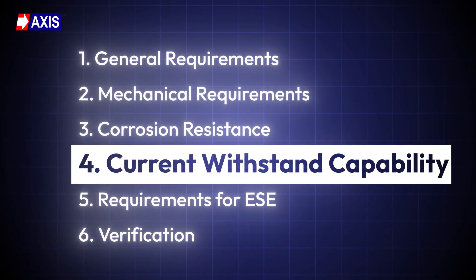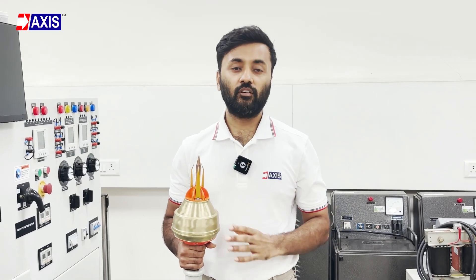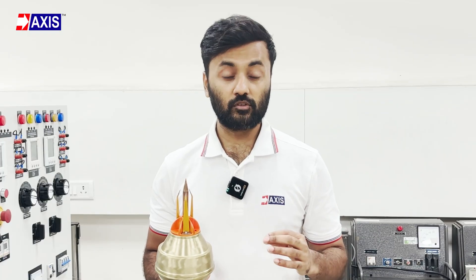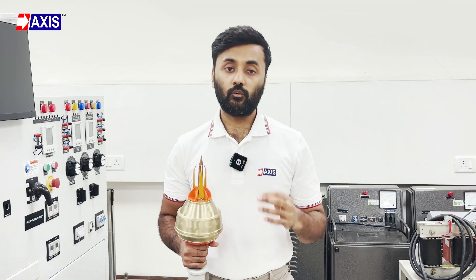Fourth, current withstand capability: this test ensures the arrester can survive a real lightning strike. They create a test current that acts like lightning — it rises very fast within 10 microseconds and reaches up to 100 kiloamperes, then slowly fades over 350 microseconds. The arrester is hit with this current three times. If it keeps working after all three, it passes the test. After the test, it must not have any damage or holes — burn marks on the surface are acceptable. These checks prove that the arrester can carry real lightning current without failing.